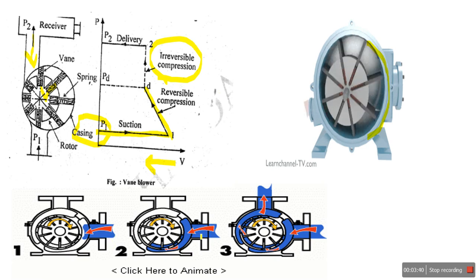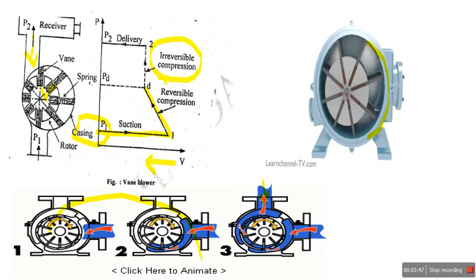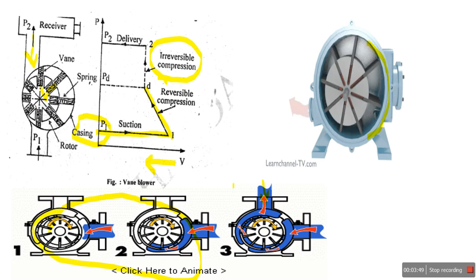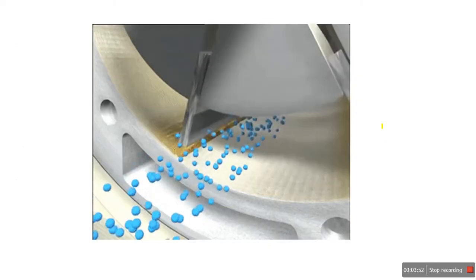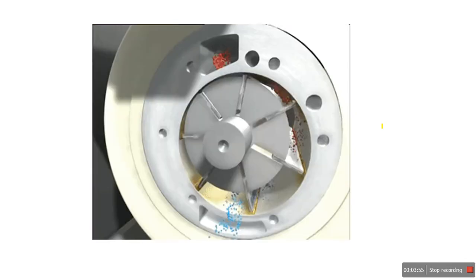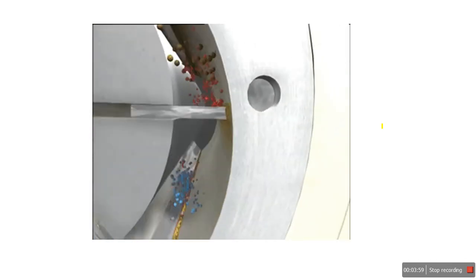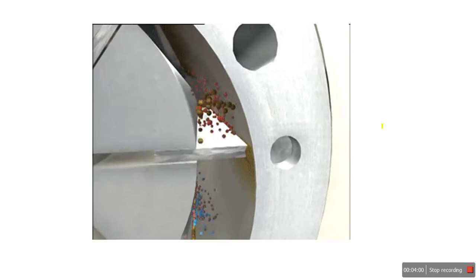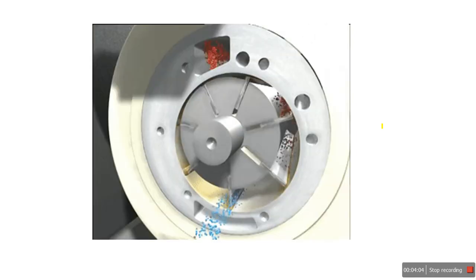Step by step: first the air is trapped, then in the second step it begins to compress, and in the third step the channel opens to the receiver for delivery. The first two stages involve volume reduction to compress the air. The animation also shows how the vanes reciprocate against the springs, how the rotor is located eccentrically, and how the compressed pockets turn red as compression proceeds.